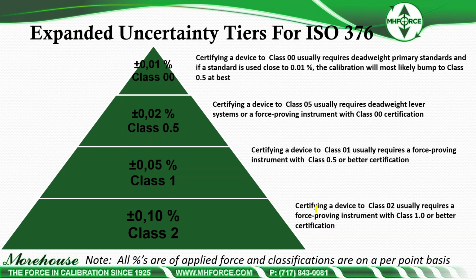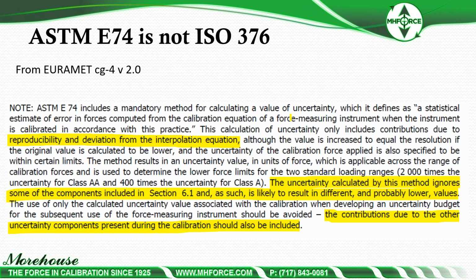So certifying the device to class 2 usually requires a force proving instrument that's class 1 or better. So usually you need a class 1 or better to certify class 2, obviously. Usually a class half is what's typically required. And then there's a nice write-up at the end of this. If you haven't read it and you're interested to learn a lot more about ISO 376 besides reading the standard, I recommend, it's free to download, EURAMET cg-4 version 2. And that describes the difference really between ASTM and ISO 376.